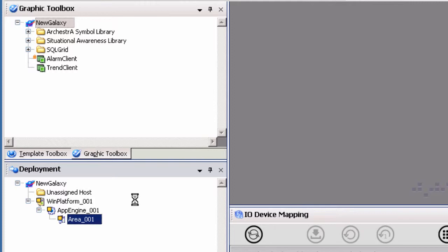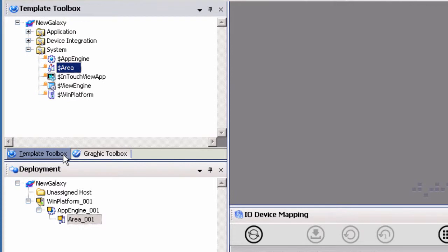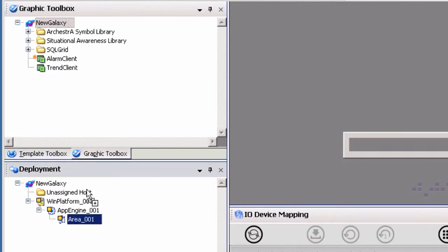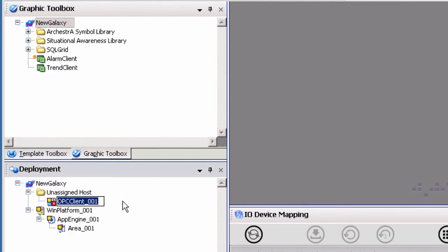Now that all of the system objects are created and assigned, we can configure our DI or device integration object. Begin by selecting the template object from the device integration section of the template toolbox. We will select the OPC client object template because we are making an OPC connection to TopServer. Drag and drop the OPC client template object to the unassigned host folder in the deployment view to create the DI object.